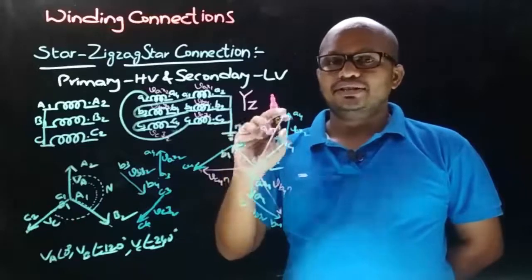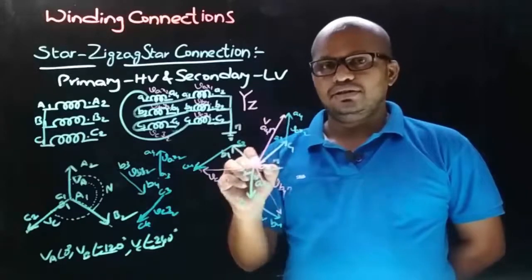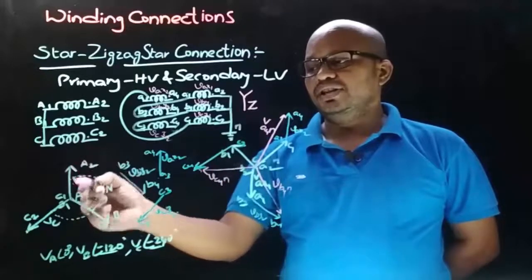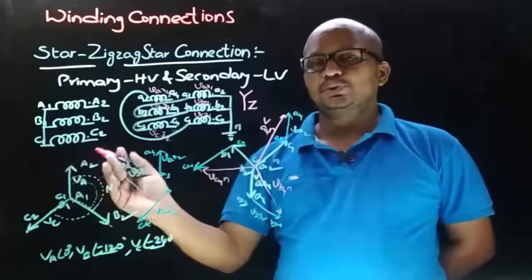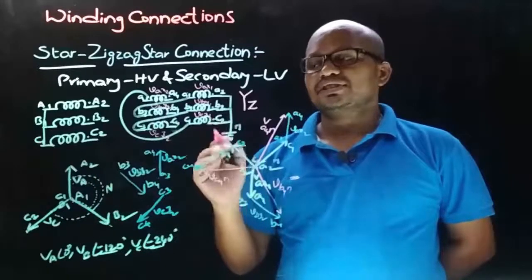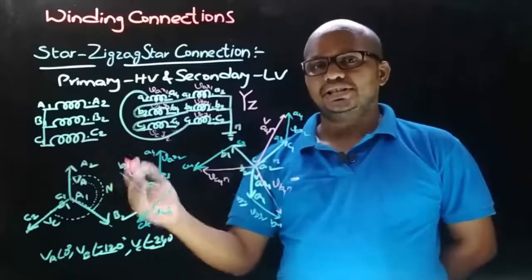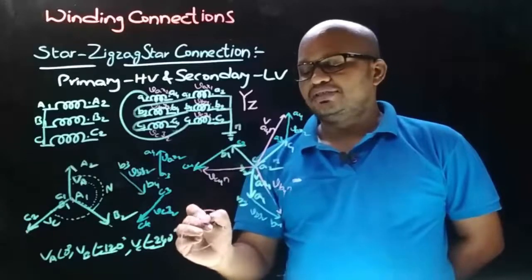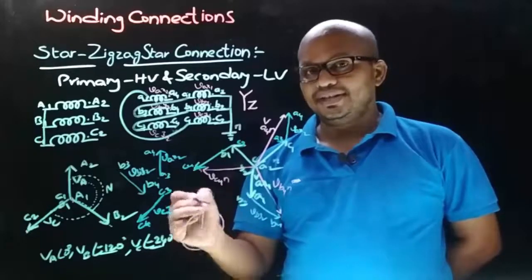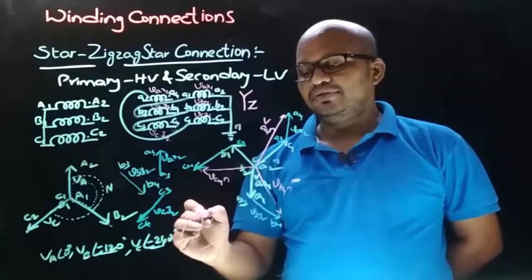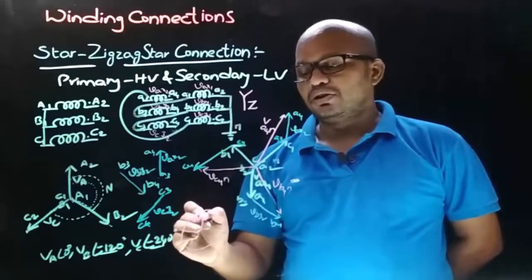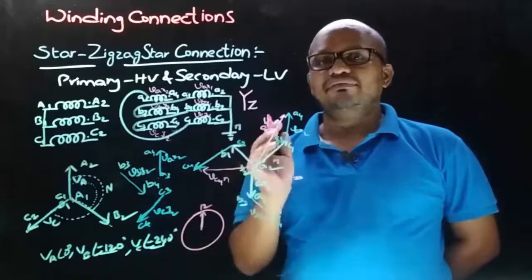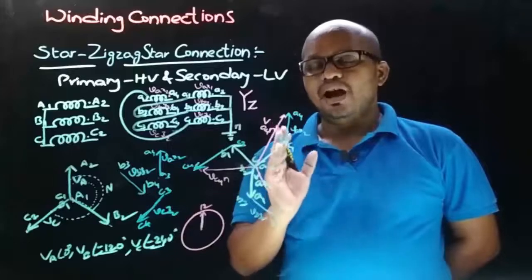So here on the LV side the phase unit voltage is VA4N, and on the HV side the phase unit voltage is A to N. In vector groups, the HV side phase unit voltage is always taken as reference, and it is indicated by the minute needle in a clock. Therefore, if you consider this as a clock, then as the HV side phase unit voltage is taken as reference and represented with the minute needle, the minute needle is always shown pointing towards 12, and in vector groups the LV side phase unit voltage is represented with the hour needle in the clock.